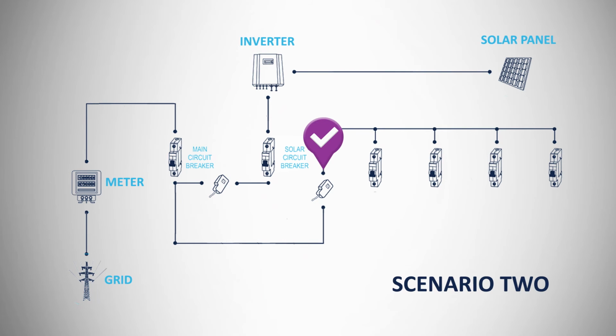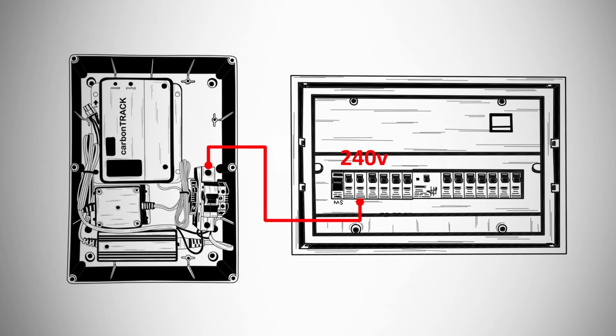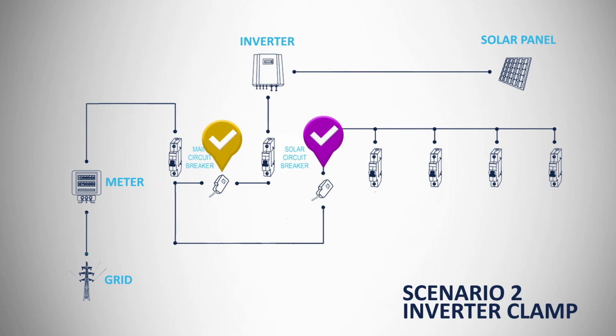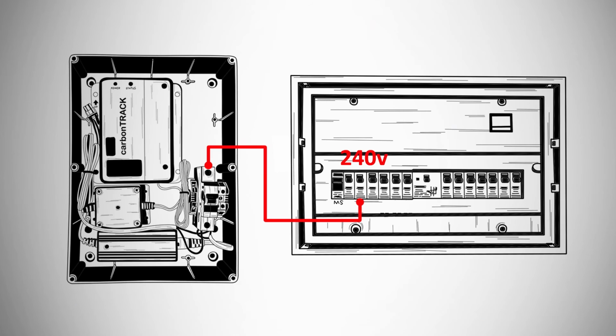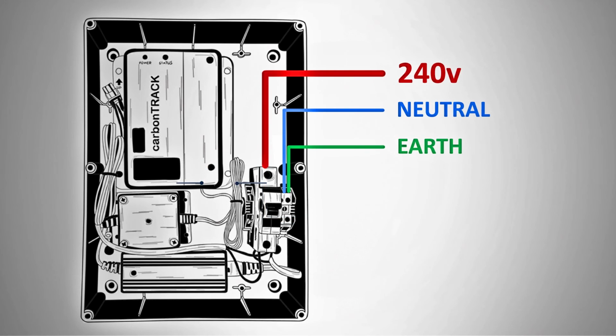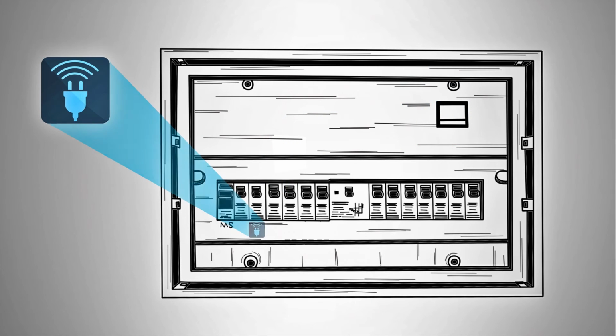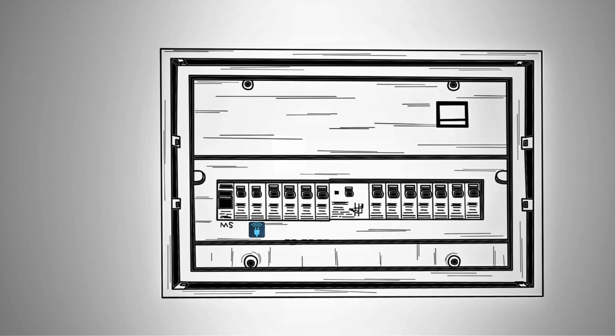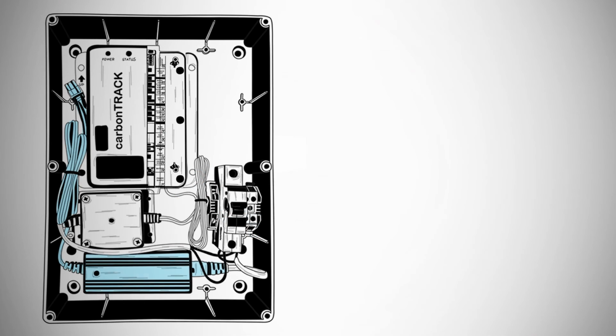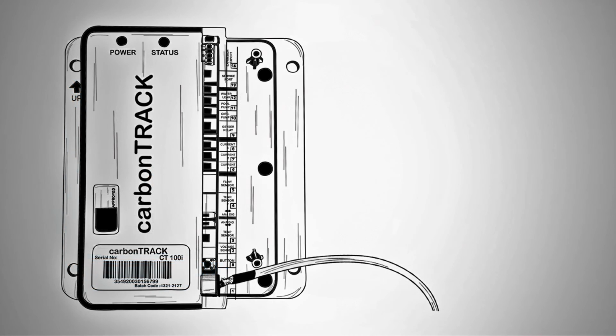To power the CT100i, run 240 volts from a suitable breaker in the distribution board to the circuit breaker inside the enclosure. Connect neutral and terminate earth. Next, stick a carbonTRACK label on the circuit breaker from where you got 240 volts. Next, plug the power supply connector into port number 1 of the CT100i.